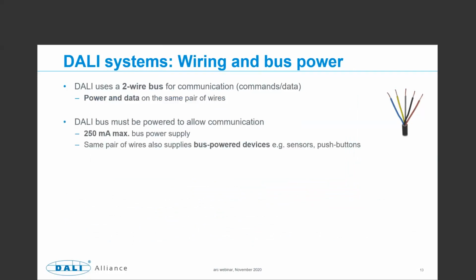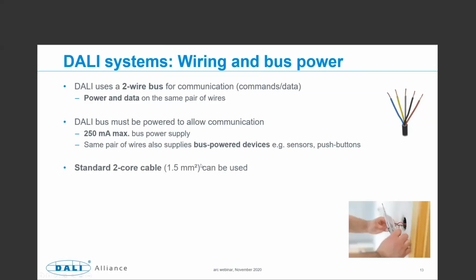The DALI bus must be powered to allow communication, and you can have up to 250 milliamps supplied to the DALI bus from the bus power supplies. Now that can be used to power bus-powered devices such as sensors and push-button controls. The cable itself is 2-core, and 1.5 square millimeters is recommended. And with that, it allows the maximum recommended distance of 300 meters between the furthest apart devices.